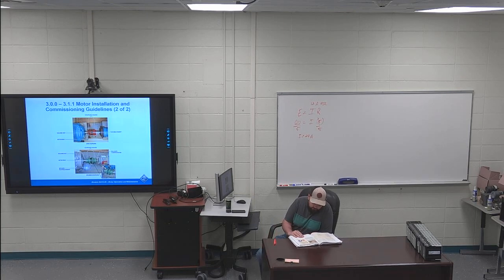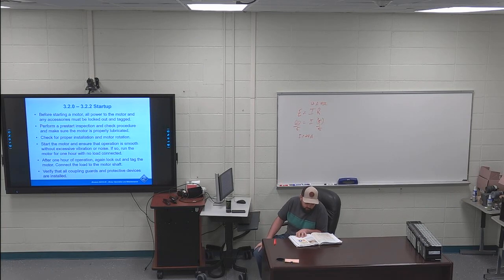Coupled startup. So once you couple the motor and start it up, you're going to check for certain things. The first four sentences are highlighted in 322. The first coupled startup should be with no load applied to the driven equipment. Apply power and check the operating current in each phase of the motor. Verify the driven equipment is not transmitting excessive vibration back to the motor through the coupling or the foundation. Vibration should be minimal. If not, balancing the load, such as a large blower wheel, may be required.